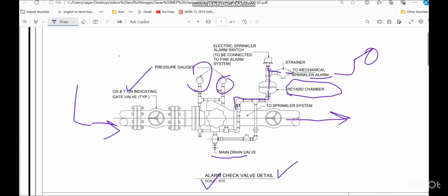Here we are mainly providing the retard chamber because, if there is any minor leakage in the system, an unnecessary alarm should not happen. So if there is any small leakage, the water will go to the retard chamber. Some amount of water will be collected here. It will avoid the false alarm. But when plenty of water is going to the system, this water will quickly fill the retard chamber, and then it will make the alarm. So this is to avoid the false alarm indication in the system.